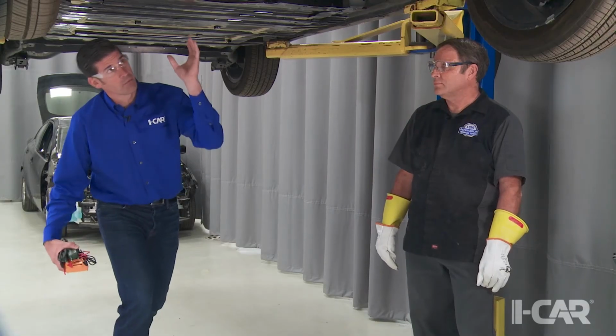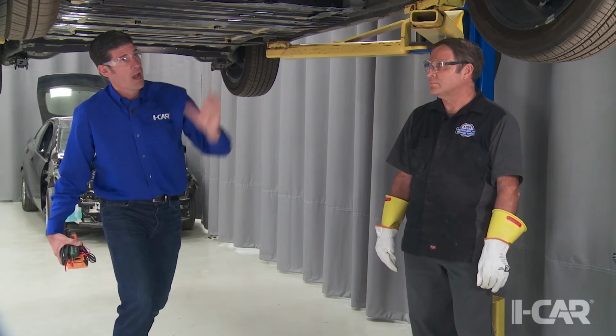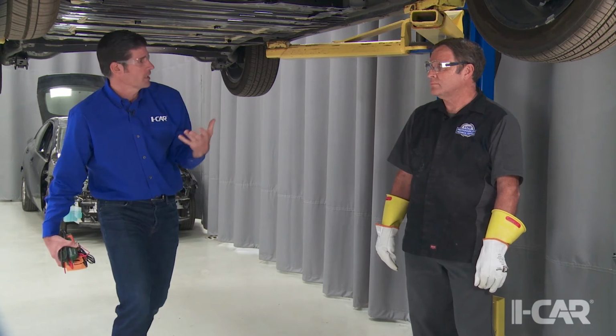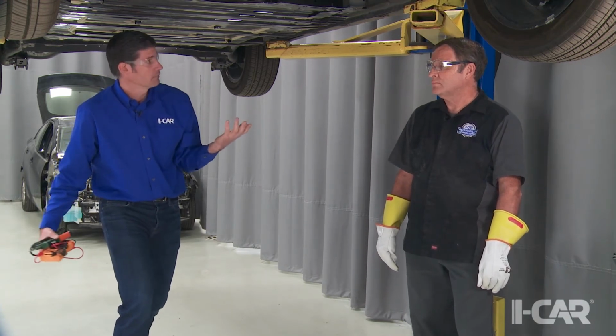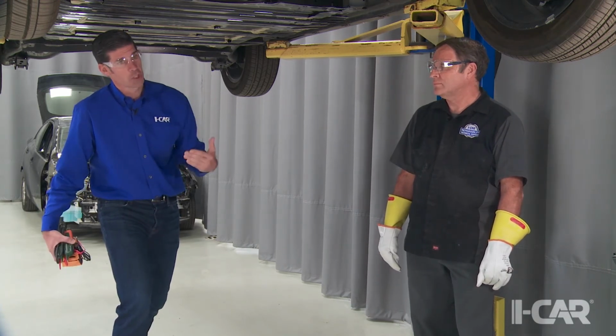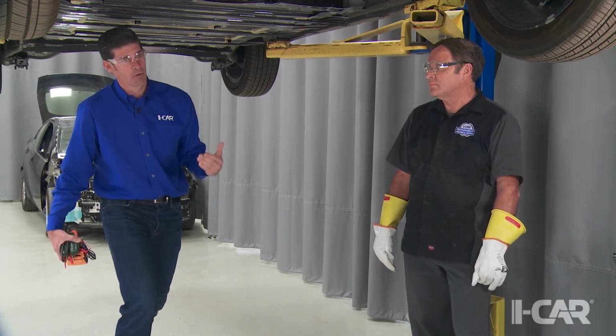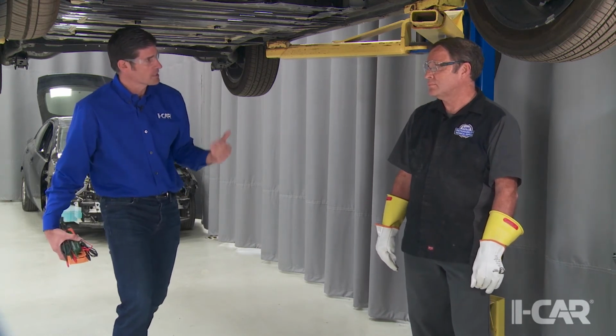When you're not doing it, we unplug the cable here. If somebody touches it, we can get electrified and die. The capacitor's discharging time is really a serious thing. When the manufacturer says 10 minutes, we have to follow those 10 minutes. There is an active and passive discharge, but that's another story.